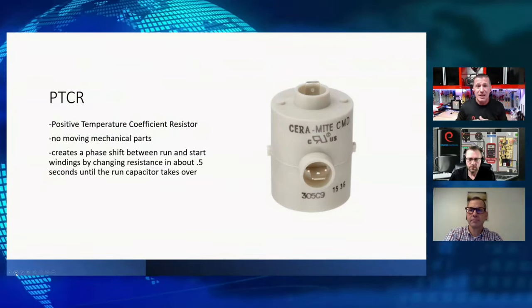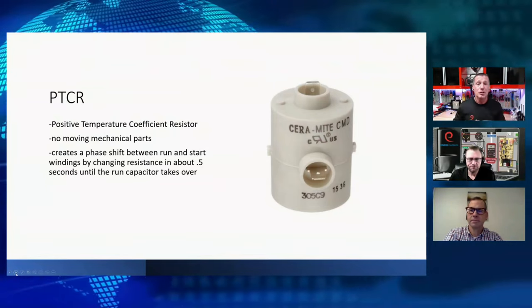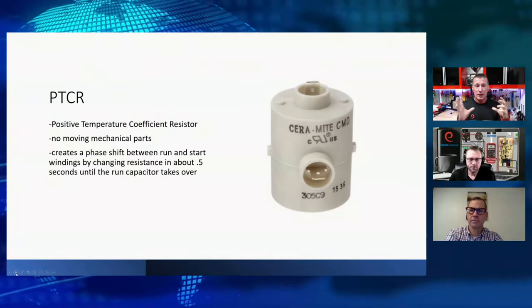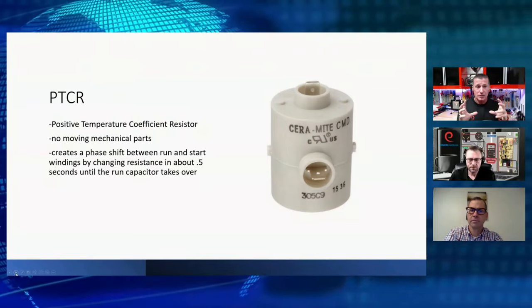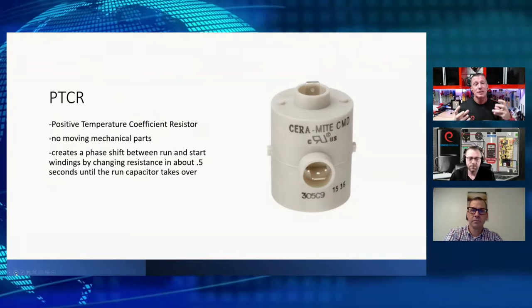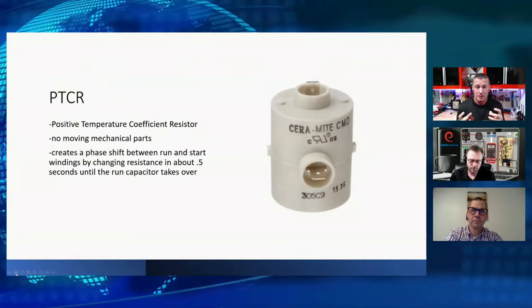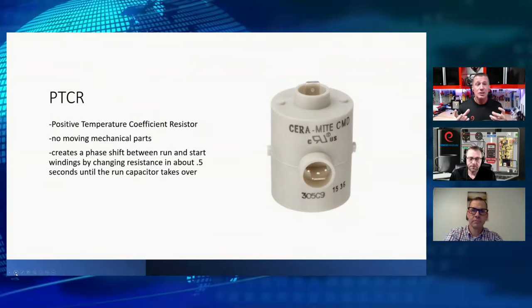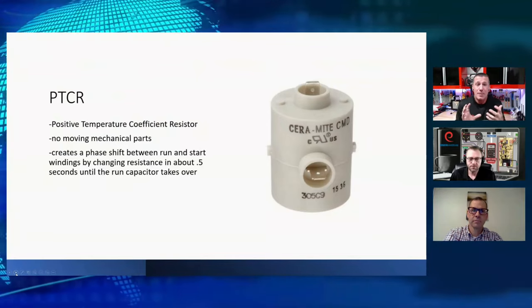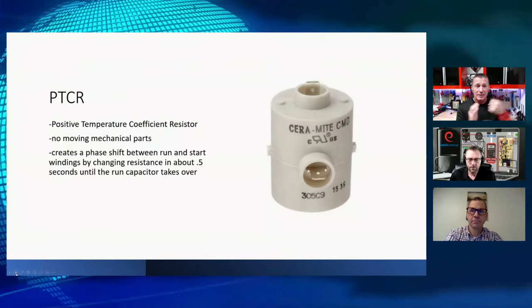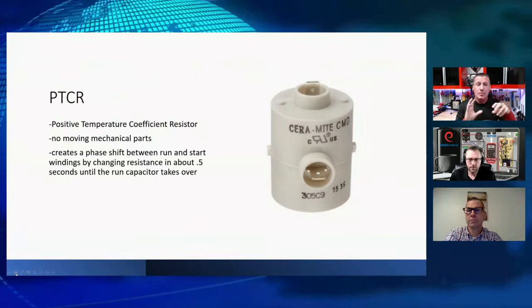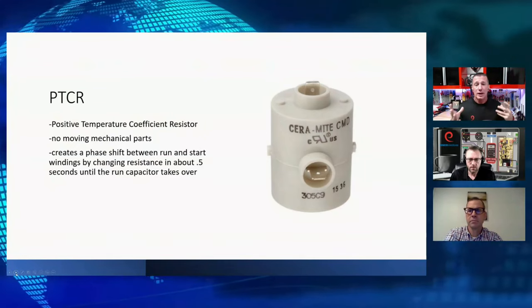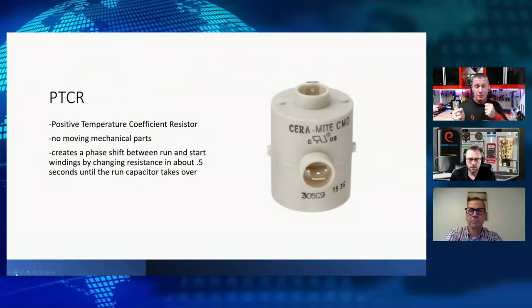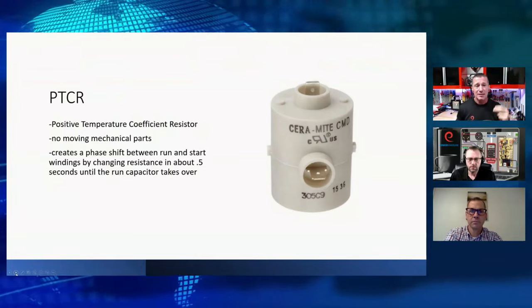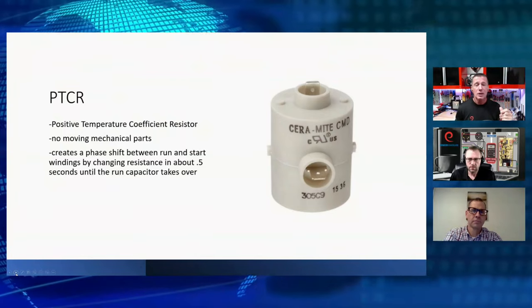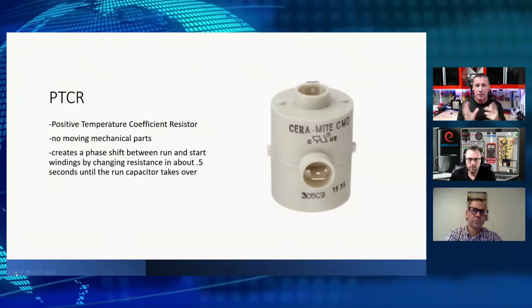Let's look at a PTCR, a positive temperature coefficient resistor. We're talking about a non-moving part, just a resistor that changes resistance based on temperature. We use that in conjunction with our run capacitor, kind of bypassing around it. As we have that inrush of current, it heats up, our current flows through, and we're able to create a phase shift between our run and start windings, usually about a half second or so, to get things moving a little quicker.